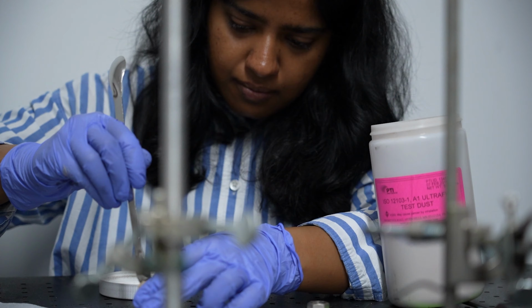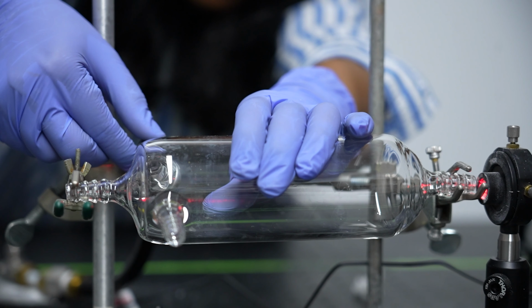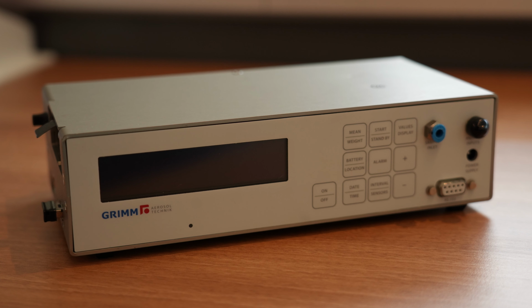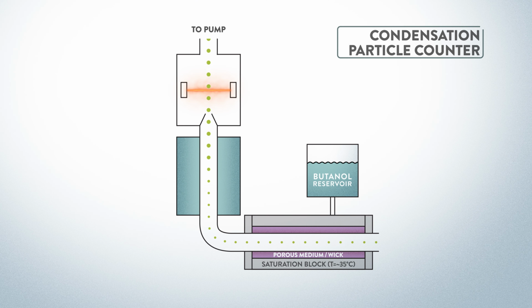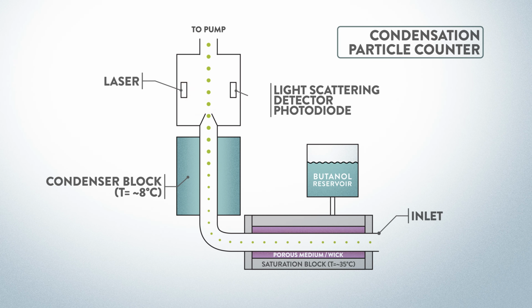Several aerosol measuring instruments work based on the light scattering principle. These instruments include condensation particle counters, aerosol optical spectrometers, particulate matter sensors, and nephelometers. With condensation particle counters, a stream of particles is drawn into an inlet. The particle size grows in a saturated environment due to the condensation of water or butanol vapors. When a laser hits the particles, light is scattered and particles are counted, providing the overall concentration.